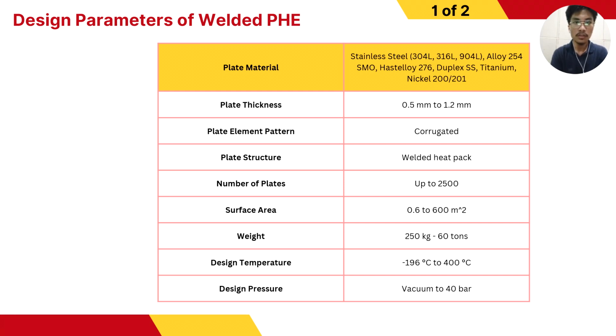Thus, it should be noted that the plate material must be carefully selected. Next, plate thickness. It can range from 0.5 millimeters to 1.2 millimeters. So when it comes to plate thickness, if it is too thin, it can cause the plate to be easily deformed. However, if it is too thick, the plate can decrease the heat transfer efficiency of the overall plate heat exchanger.